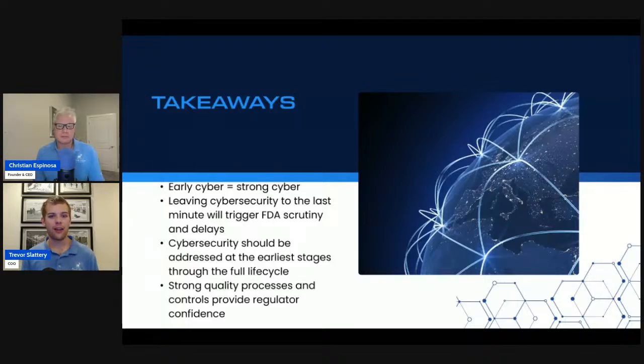This is going to tie us right into our second point, where leaving cybersecurity to the last minute is what can trigger FDA scrutiny, delays in your submission, and then problems going through into a cleared product with your go-to-market strategy. We want to see cybersecurity treated as a total product lifecycle consideration, addressed from the very earliest stages all the way down to disposal of the product. To provide evidence of this, we need to make sure that we have strong quality processes and strong controls in place that are going to provide that regulatory confidence and make sure that we're going through with our FDA submissions with no problems and no delays.